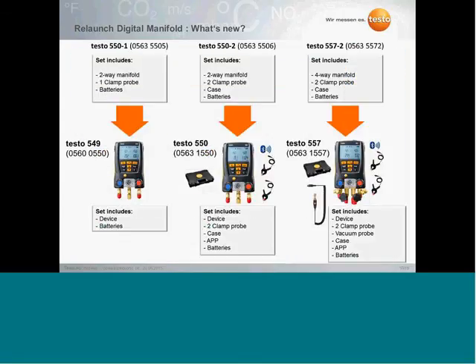On the upper part, you see the existing, actual manifolds, and below you see the new relaunched manifolds and what they include. Starting on the left side with the 549, the set includes only the device and batteries. In the middle, you see the Testo-550, which includes the device, 2 clamp probes to measure temperature, and the app and Bluetooth functionality. And on the right side, you see the 557, which also includes the temperature probes, the case, the app, and in addition the set includes an extra vacuum probe to make a safe evacuation of your system.